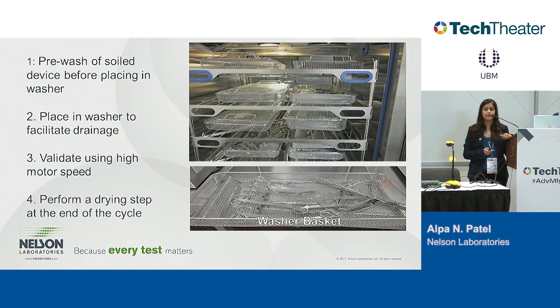Some of the key things to remember for automated cleaning: you want to perform a pre-wash of all soiled devices before placing them in the washer, like manual rinsing under tap water, very important. Once you place the device into the washer, place it in a way that facilitates drainage, and validate using high motor speed. We just had an incident last year where a sponsor was using low motor speed, and they were failing all of their automated cleaning because it was low motor. But once they pushed it to high motor, because that's what the healthcare facilities use, everything worked out really well. And always perform a drying step for the automated cleaning. These are the 4 success steps for any automated cleaning. If you do all these 4, you should be able to have a pass, or at least something that gives you an idea that you're going in the right direction.